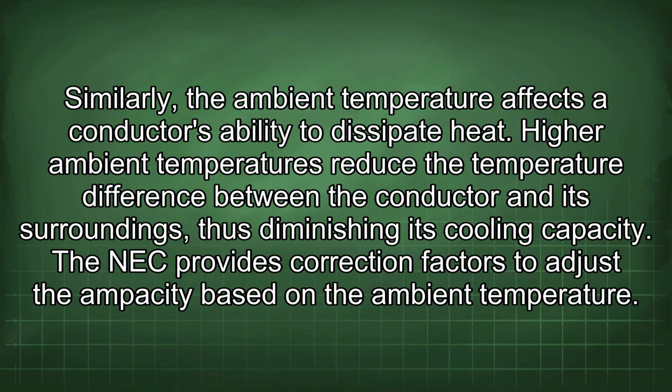Similarly, the ambient temperature affects a conductor's ability to dissipate heat. Higher ambient temperatures reduce the temperature difference between the conductor and its surroundings, thus diminishing its cooling capacity. The NEC provides correction factors to adjust the ampacity based on the ambient temperature.